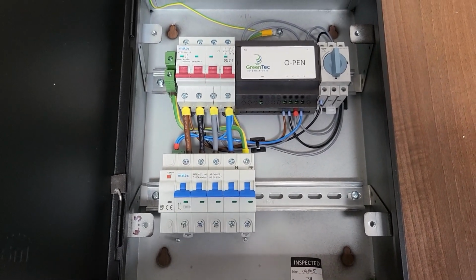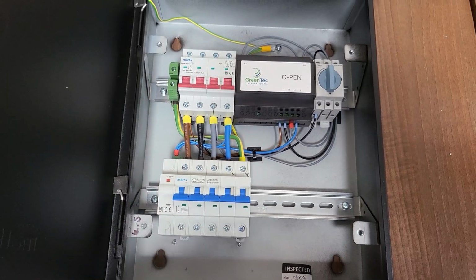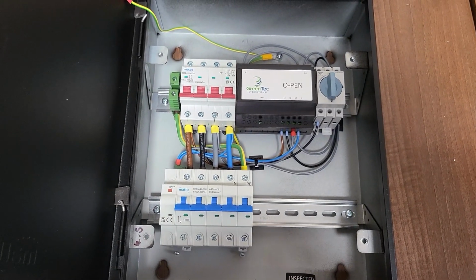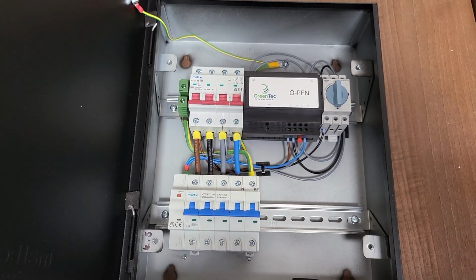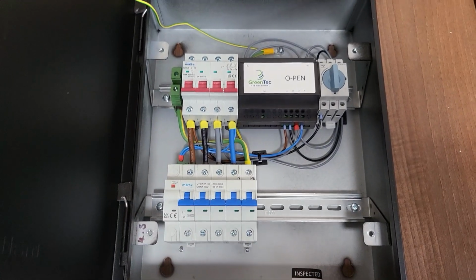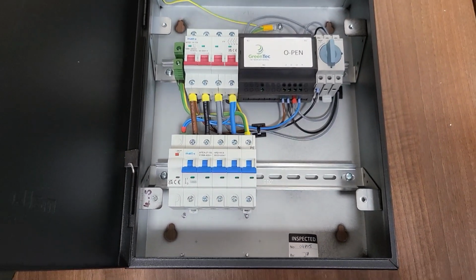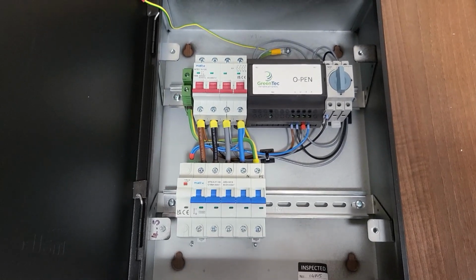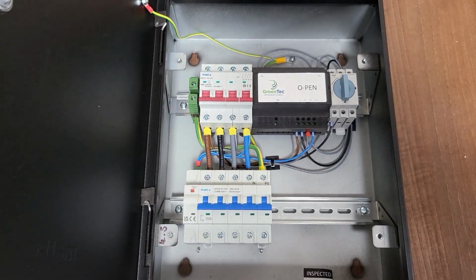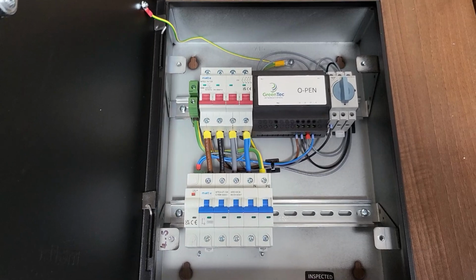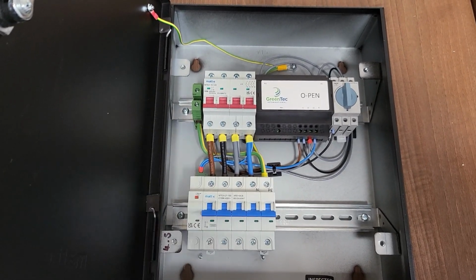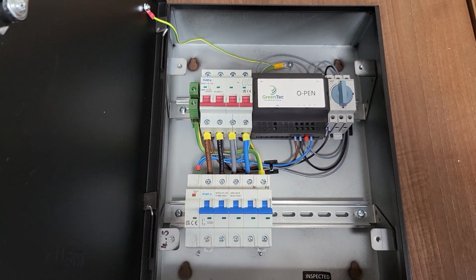Personally, I prefer to take the armorings with an earth on them down to the charge point itself and then isolate that from the charge point, so there's no possibility of it being exported onto the charger, but equally you have some earth metallic protection on the cable leading down there. There are different ways of doing it. Let's jump back to the desk and have a run through the manual.